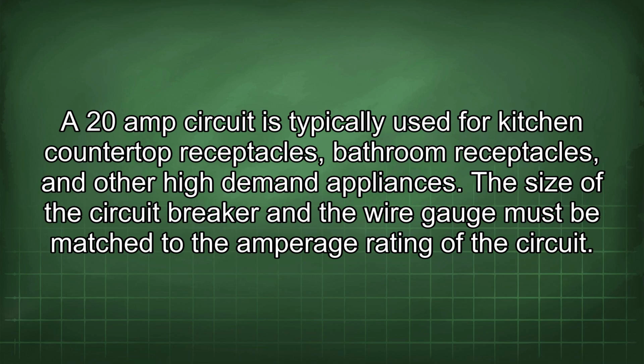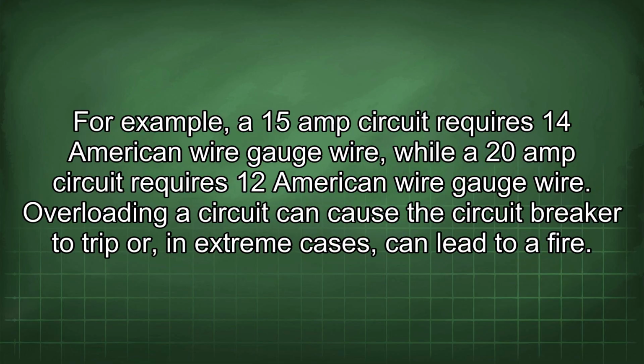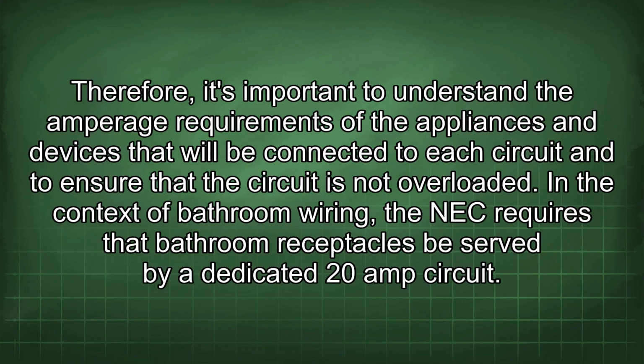The size of the circuit breaker and the wire gauge must be matched to the amperage rating of the circuit. For example, a 15 amp circuit requires 14 American wire gauge wire, while a 20 amp circuit requires 12 American wire gauge wire. Overloading a circuit can cause the circuit breaker to trip or, in extreme cases, can lead to a fire. Therefore, it's important to understand the amperage requirements of the appliances and devices that will be connected to each circuit and to ensure that the circuit is not overloaded.